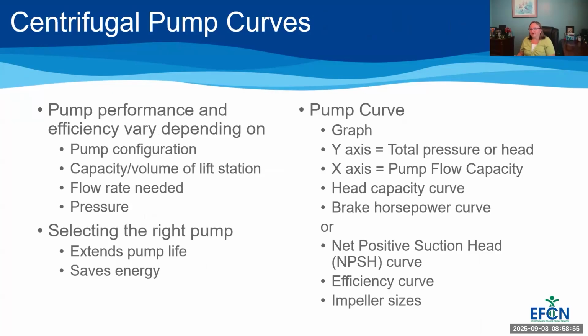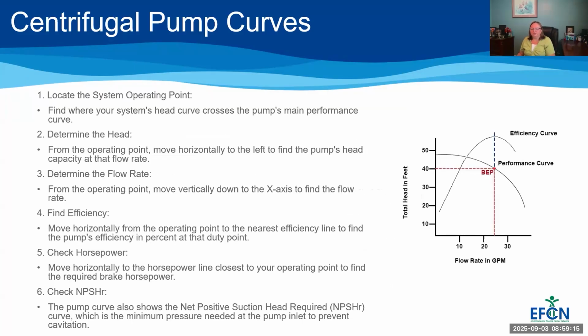Centrifugal pump curves. So pump performance depends on your flow rate needed and your pressure. So your pump curve is going to show you those things. It's a graph. It has a y-axis and an x-axis, and then there's other things that might be on the graph. And so there's ways to read the centrifugal pump curve. And I do have some handouts that I'll put in the chat as soon as we're done here, so you can see them. They'll also be uploaded on our website. But just being familiar with what's on a pump curve and why you would need one to make sure that you're selecting an efficient, correctly sized pump.